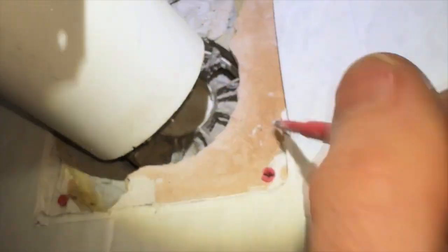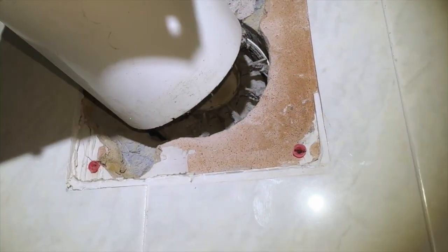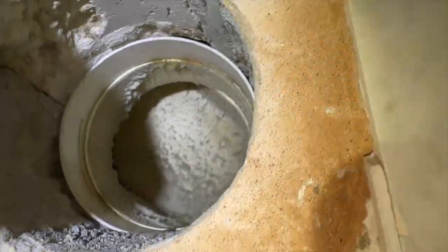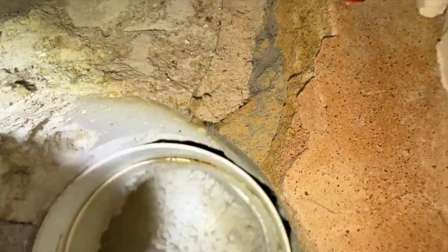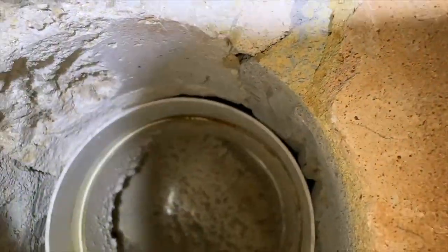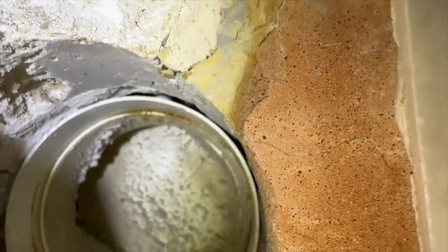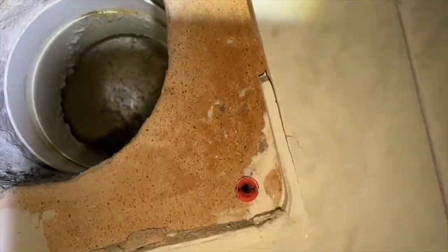The backflow shutter doesn't look like it's been opening. Oh, right. Okay. So when that stays closed, you're not getting any airflow. So it's going straight onto a U-bend or an elbow, and it wasn't a very efficient duct. I think that's possibly why it stopped the backflow shutter from opening.